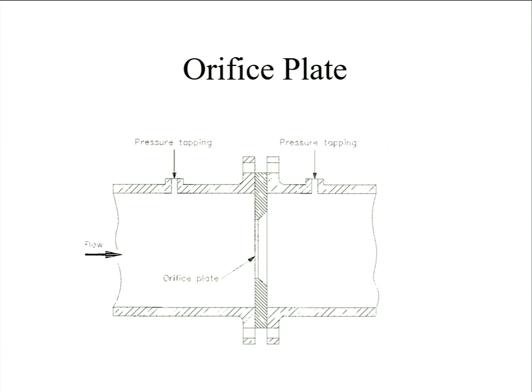So again, if you've had to put cost in to increase the pressure, you don't want to be throwing a lot of it away across an orifice plate, unless you, for some reason, are later on reducing it. But it is nice and simple. There's no moving parts to it. But you've got to keep the faces clean so they are inspected, and you don't want them getting hit by particles. So usually there's filtration upstream to keep them clean. A bit of oil on the face, or liquids, hydrocarbon liquids, hence maybe dew point control, can cause inaccuracy.